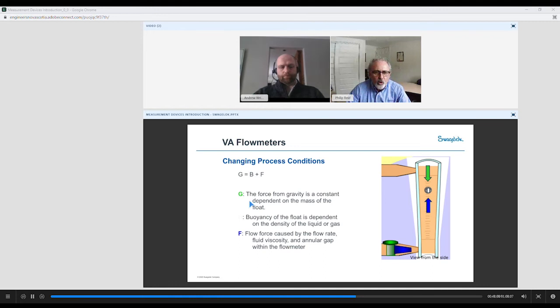Changing process conditions. So in this flow meter, we see that G equals gravity force, which is dependent on the mass of the float. Then there's buoyancy, and I guess I better pick a better letter for that, but the buoyancy of the float is dependent on the density of the liquid or gas. And then the flow force caused by the flow rate coming in, which depends on the fluid viscosity and the annular gap within the flow meter. I might just mention at this point, all our flow meters are calibrated with air or water, specific gravity of 1. I will talk a little bit about why we do that in just a minute. Most variable area flow meters, or quite a few, will have a metering valve so that you can control flow right at the front of the flow meter, and you can adjust the flow as you're reading it out.